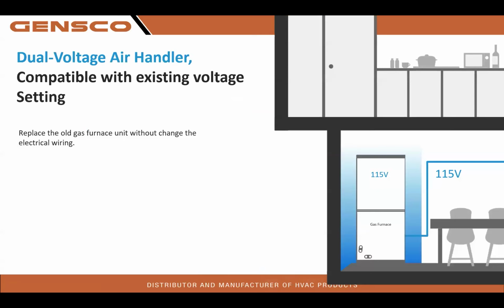What is fantastic about this equipment, specifically the air handler, is that it is dual voltage, okay? It is 115 or 208/230 volt, auto recognizing. The only time that you would actually need to land 208/230 to this air handler is if you chose to install strip heat. If you wanted to replace just a standard furnace, you could do so without adding in strip heat. Just land your 115 volts.